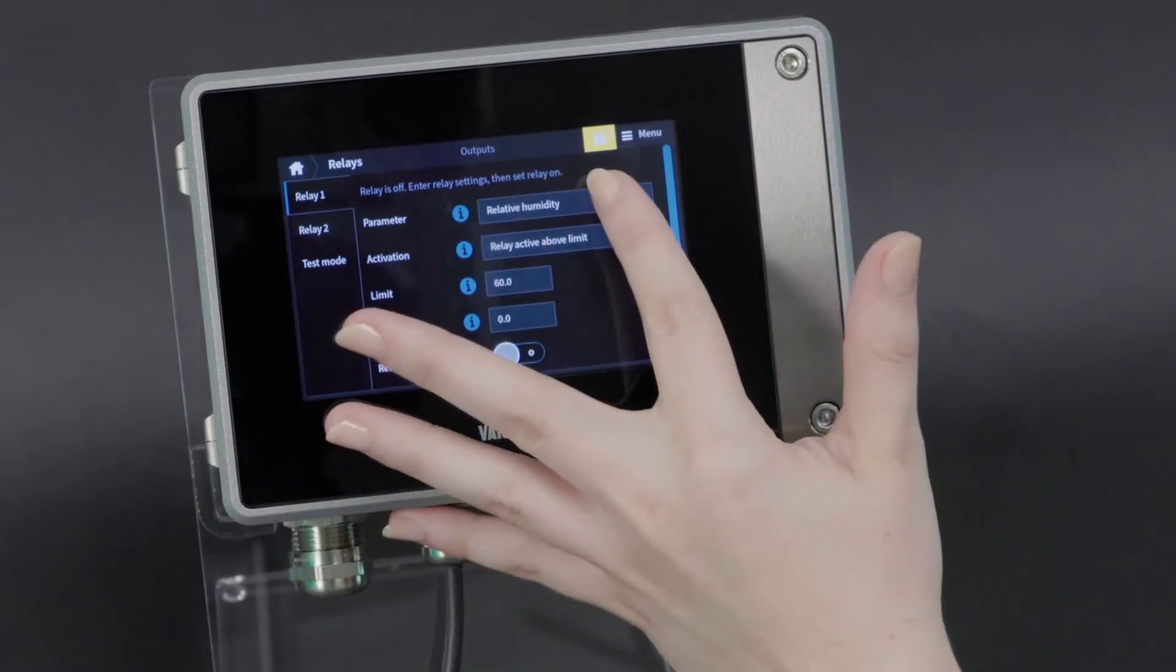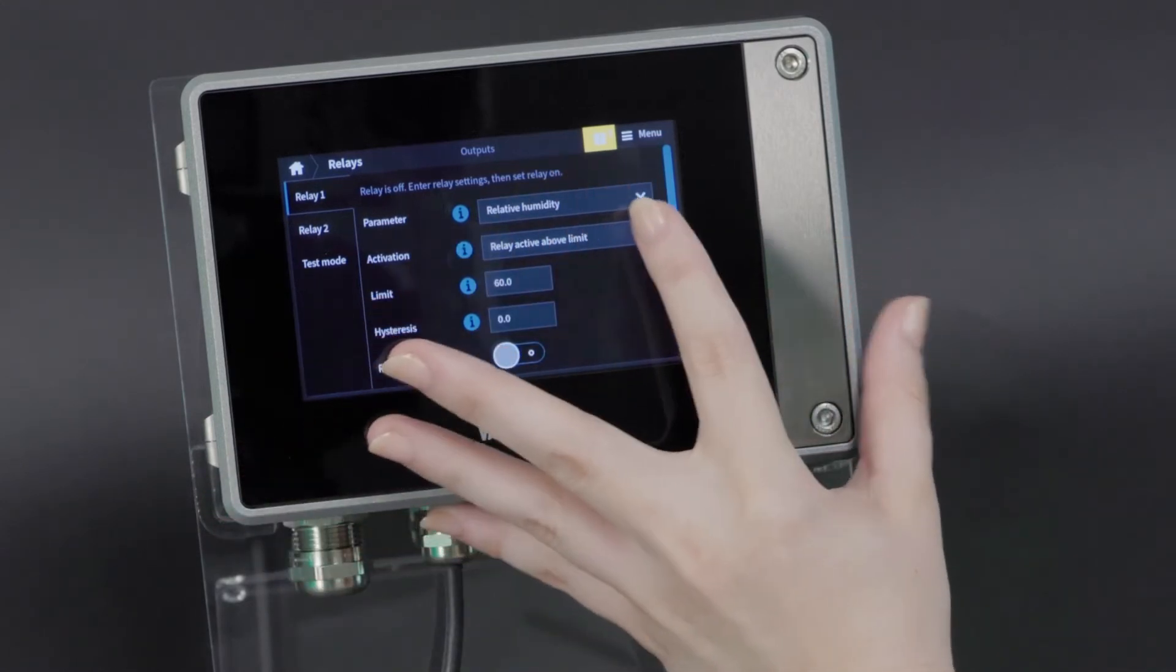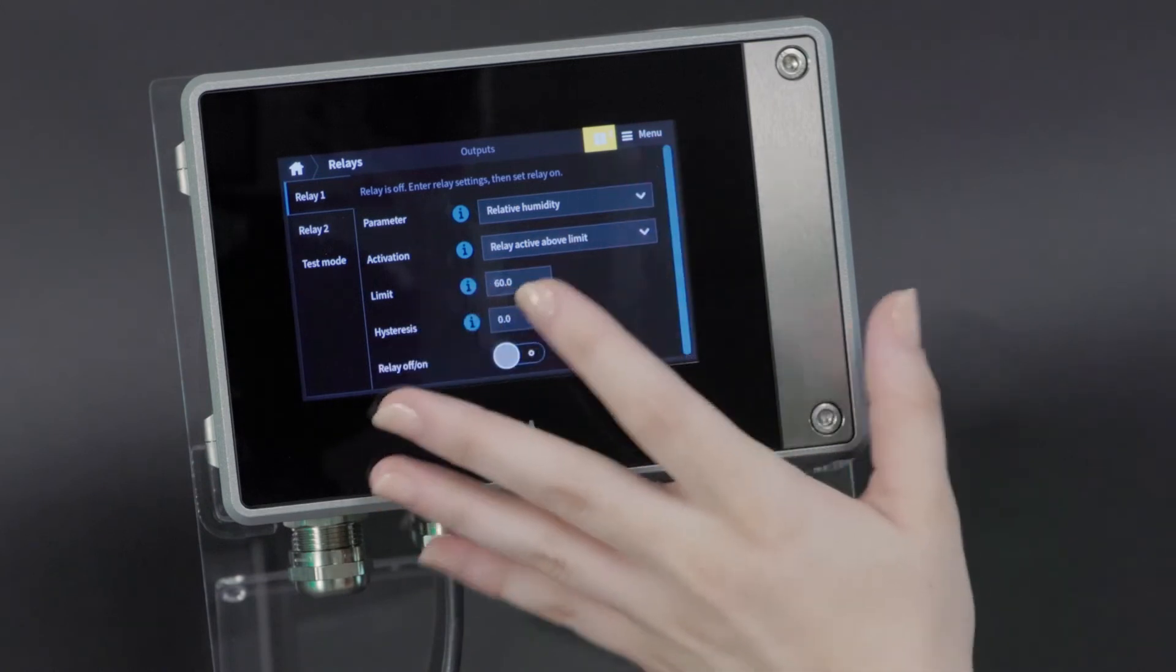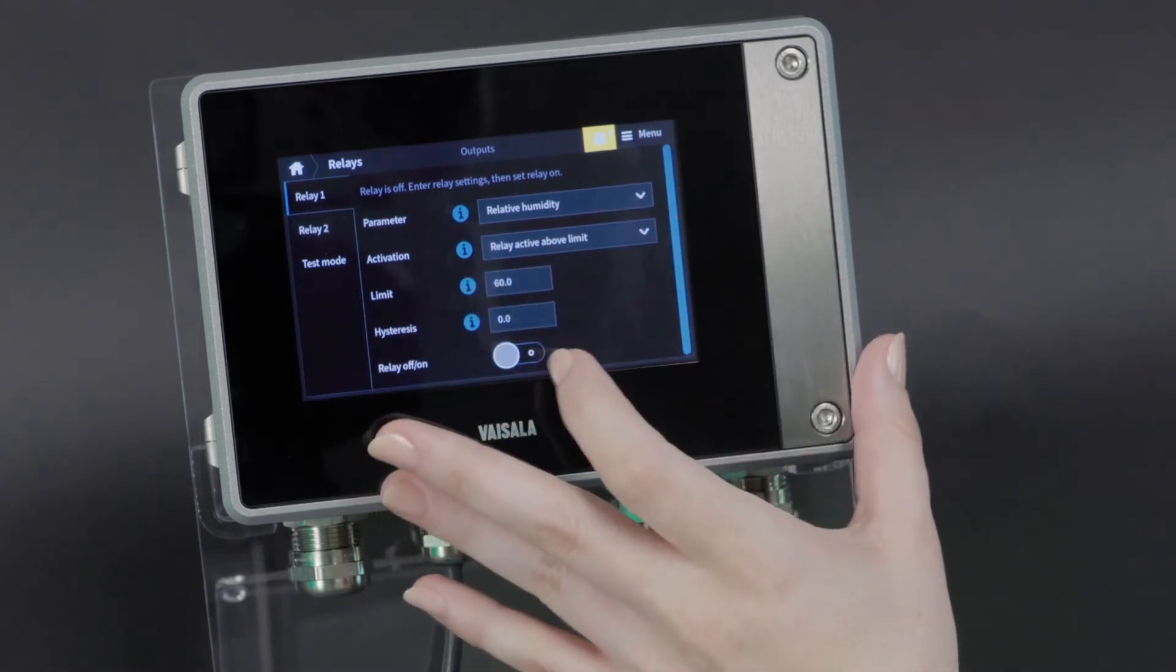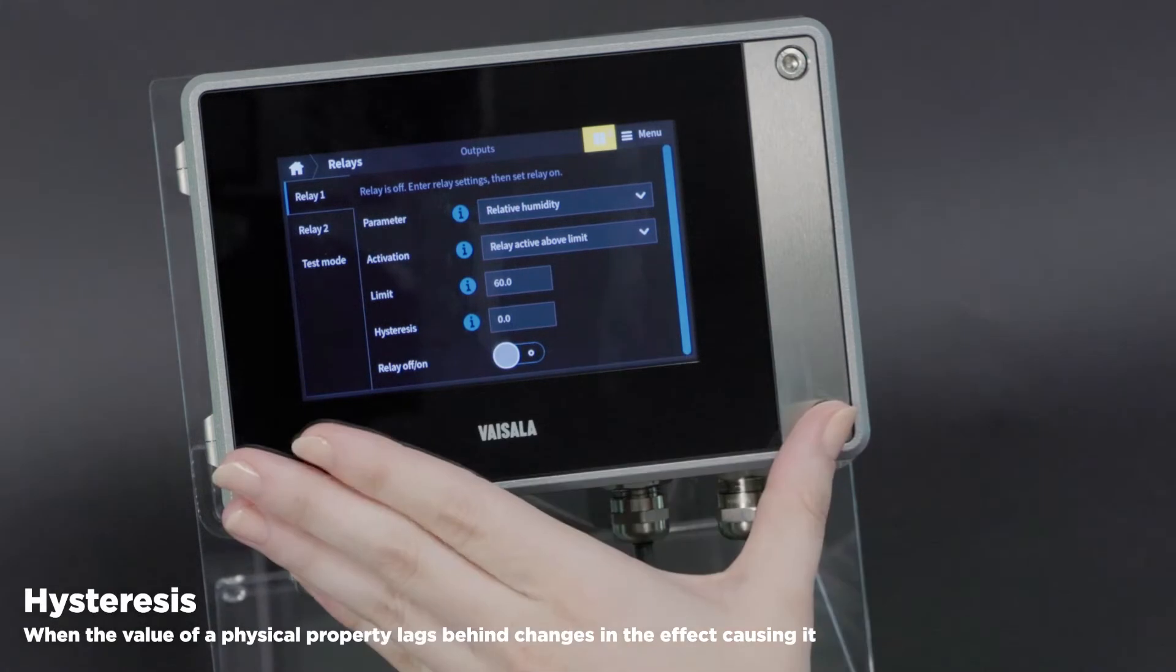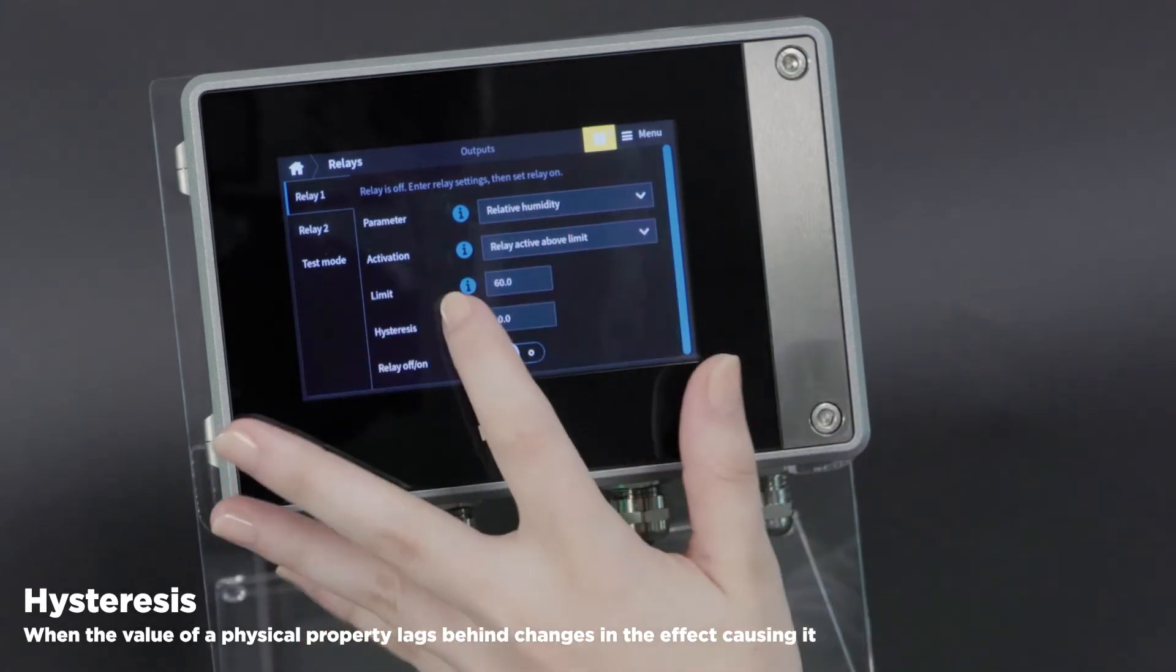There are two relays available with this instrument. You can select your parameter, whether it will be active when you go above or below the limit that you set, and then a hysteresis value. For more information on any of these options, you can click the information button for an explanation.